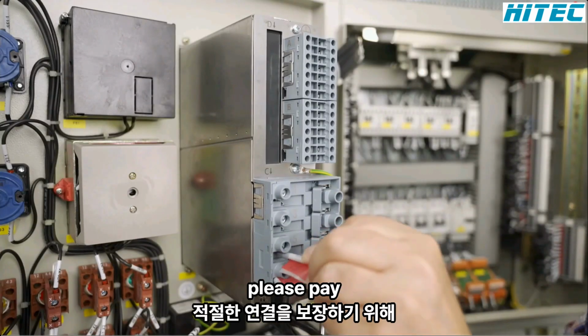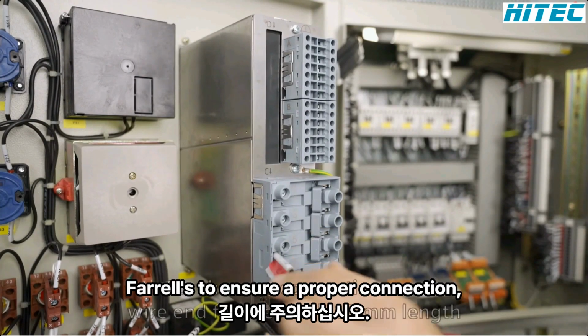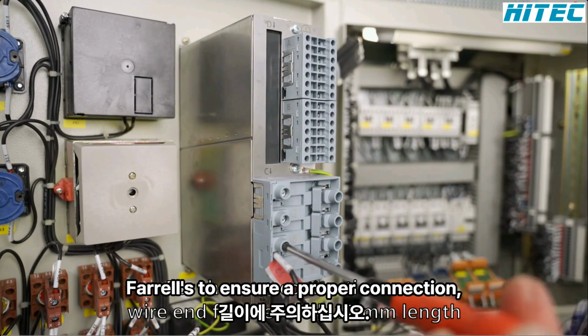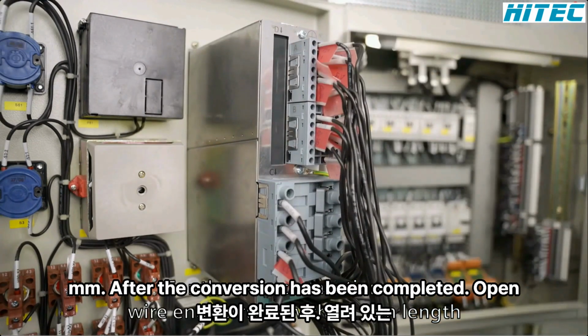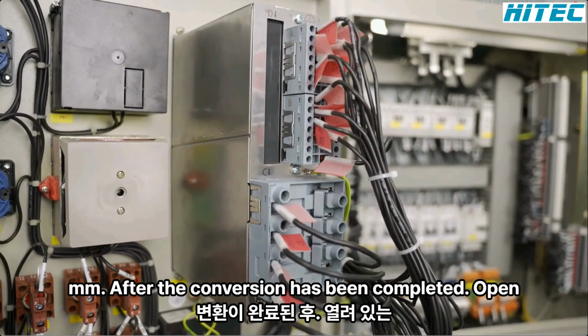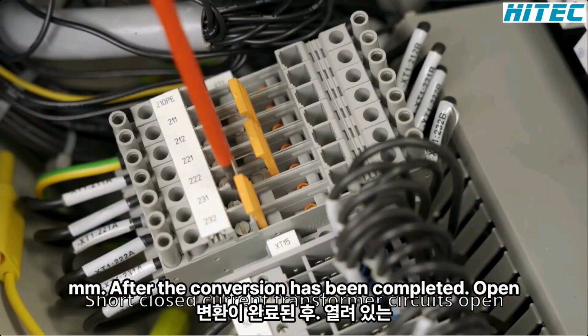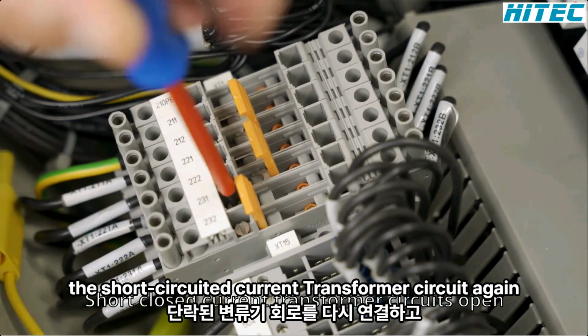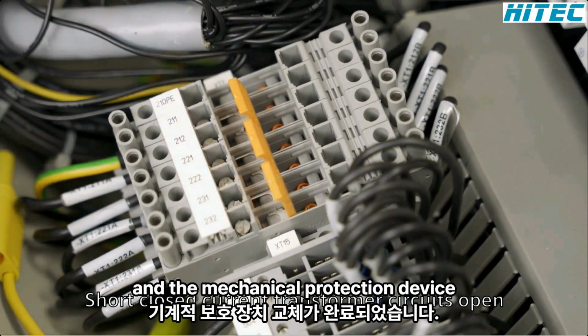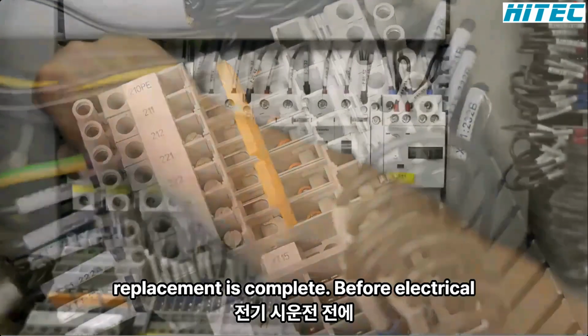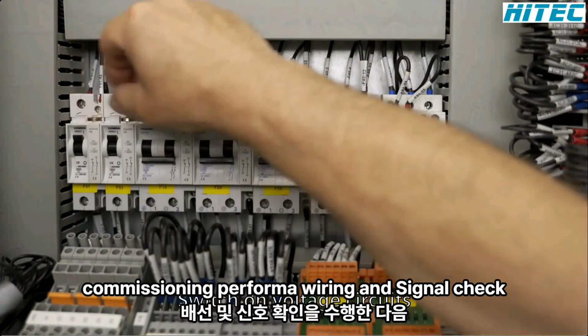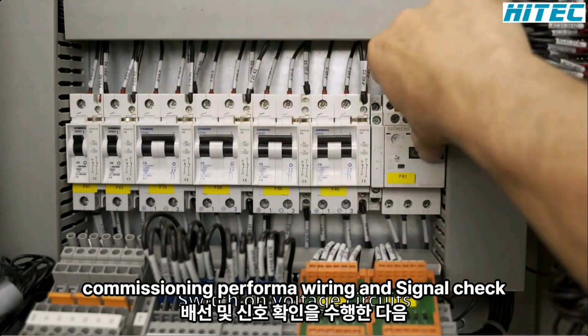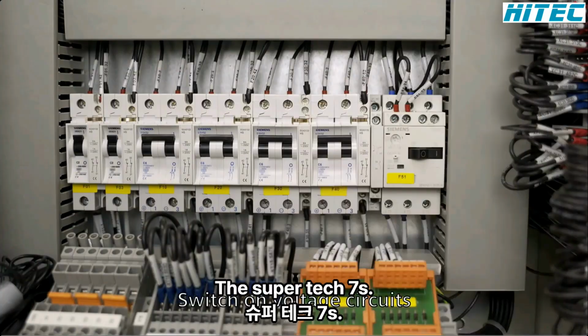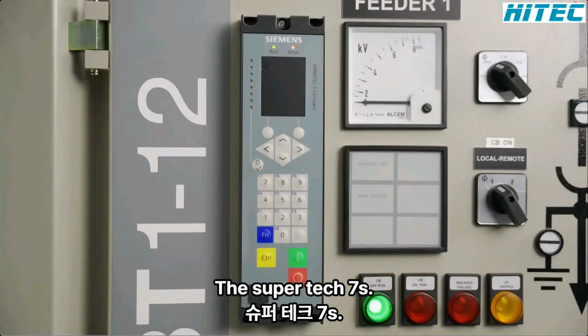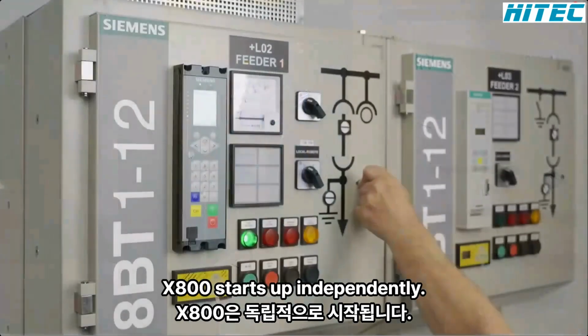When rewiring, please pay attention to the length of the wire end ferrules. To ensure a proper connection, you need wire end ferrules with a length of 12 millimeters. After the conversion has been completed, open the short-circuited current transformer circuits again and the mechanical protection device replacement is complete. Before electrical commissioning, perform a wiring and signal check, then the circuits can be reconnected. The SIPROTEC 7SX800 starts up independently.